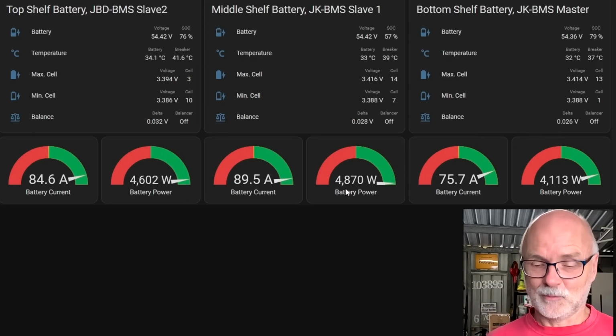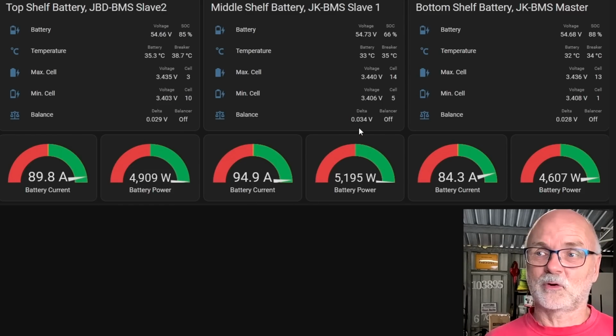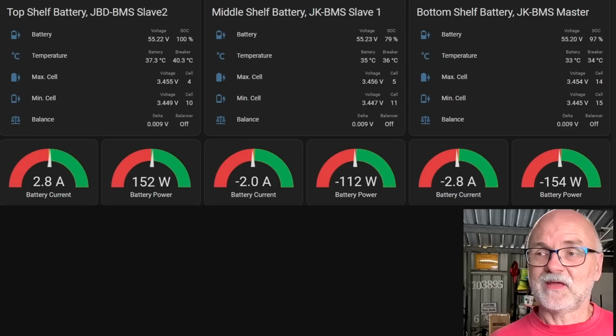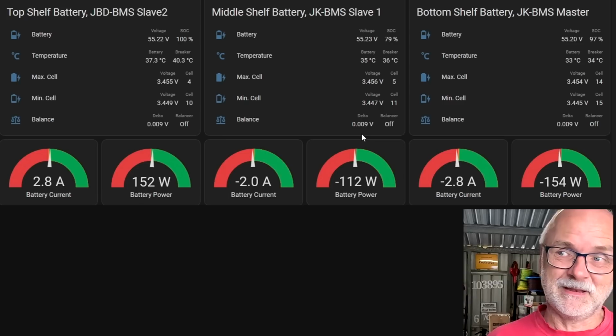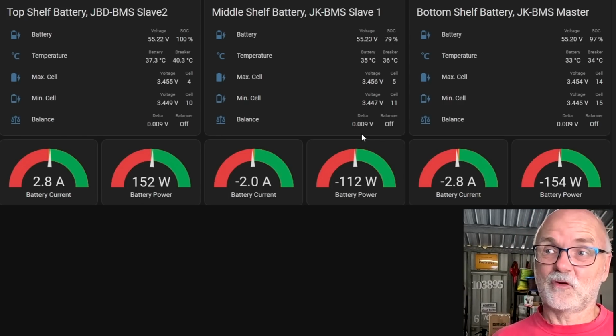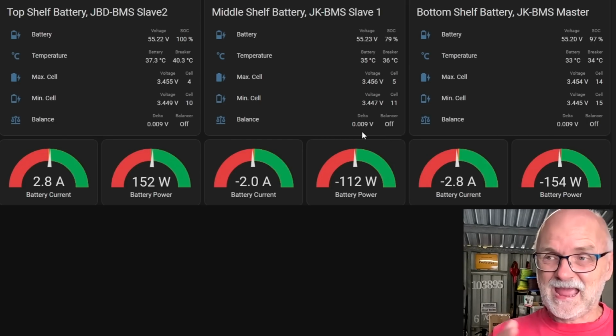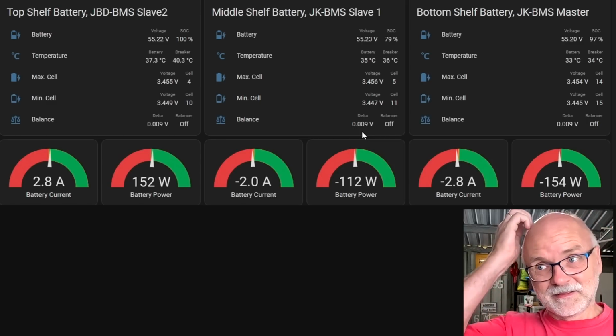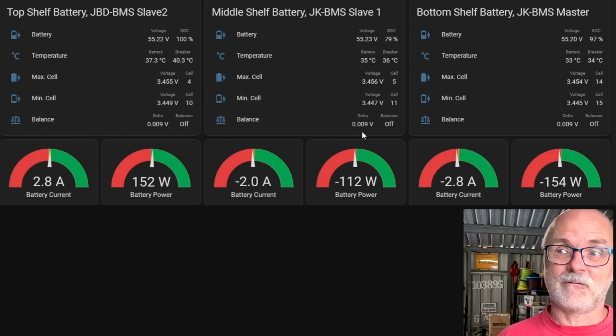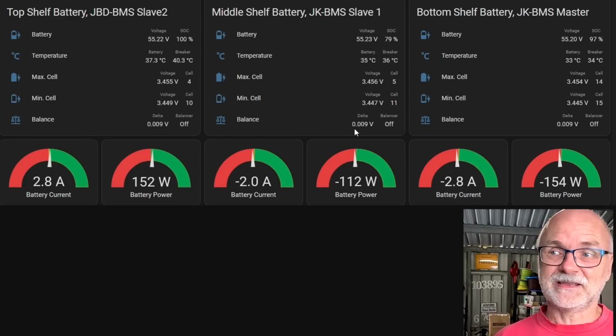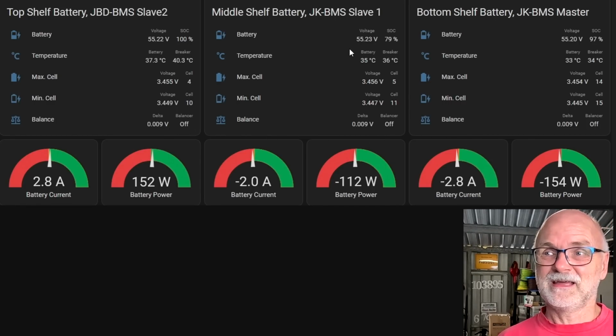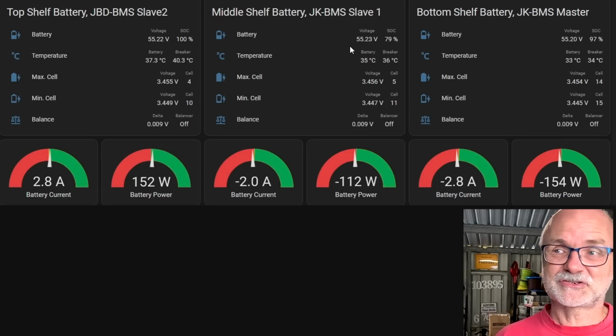At full power, 95 amps into the battery, we've got only a 34 millivolt deviation, 29 top shelf and 28 bottom shelf. Then once the battery was fully charged at 55.2 volts, we saw a deviation of under 10 millivolts, which I hadn't experienced for a very long time, because the deviation was always so high that the balancer didn't have enough time to top balance this middle shelf battery within the half hour of absorption time. Now I could see a very quick disappearance of this imbalance, and everything is fine — we're under 10 millivolts, and the balancers actually turned off here at 55.2 volts. We're 100% charged, everything is good.